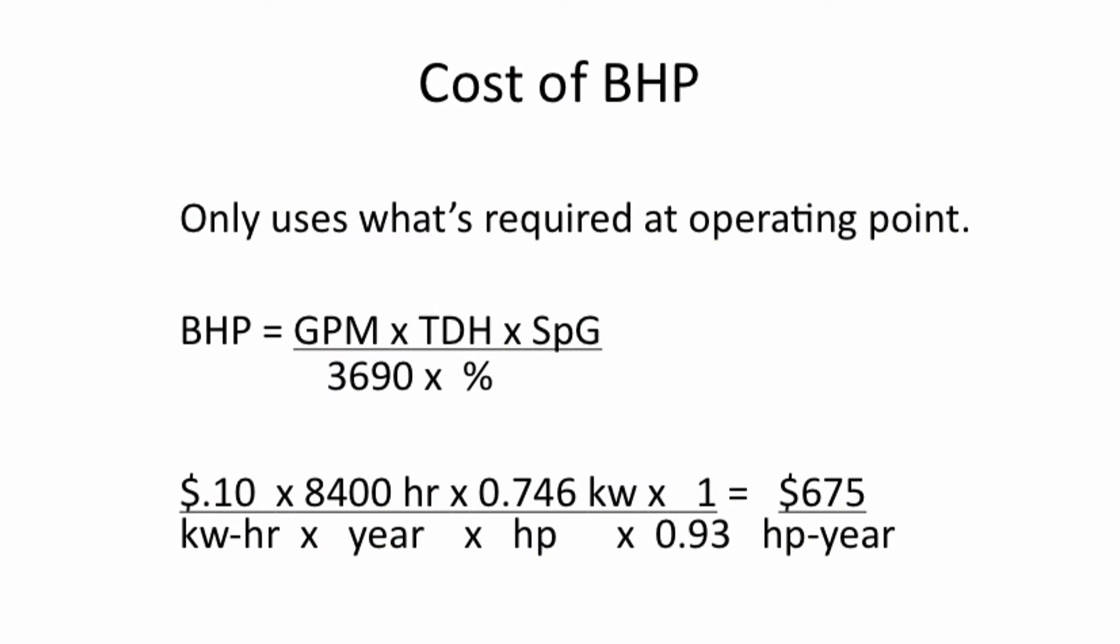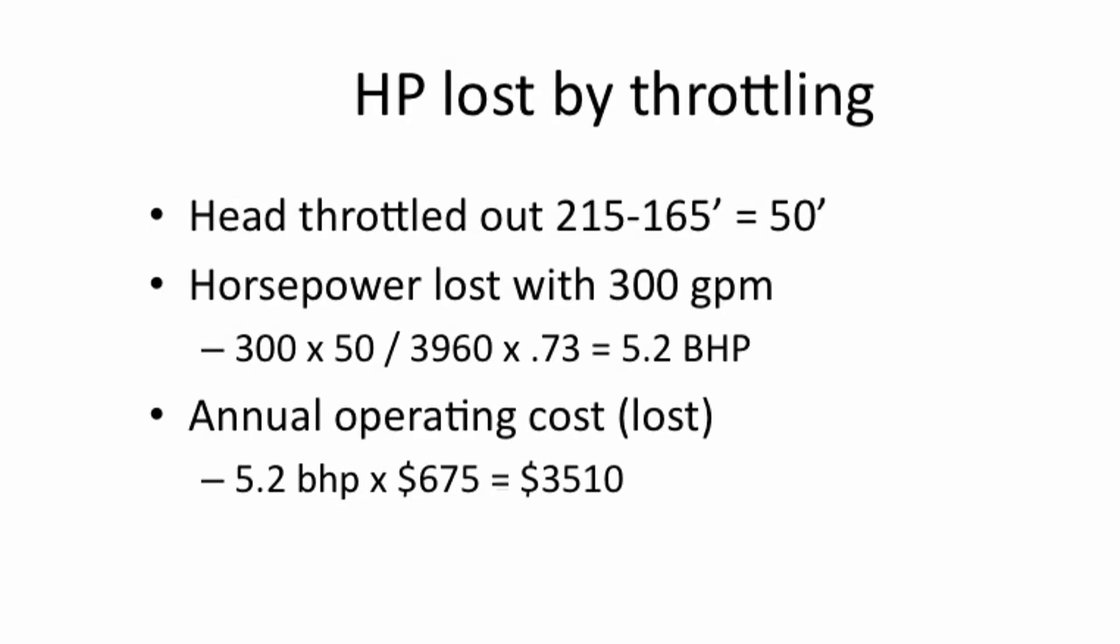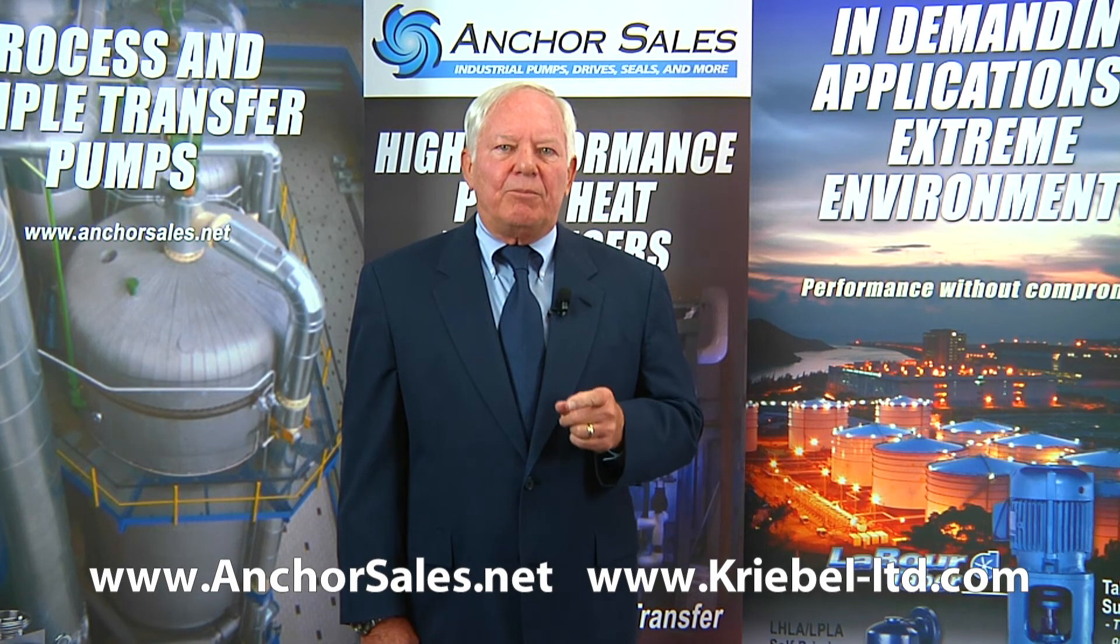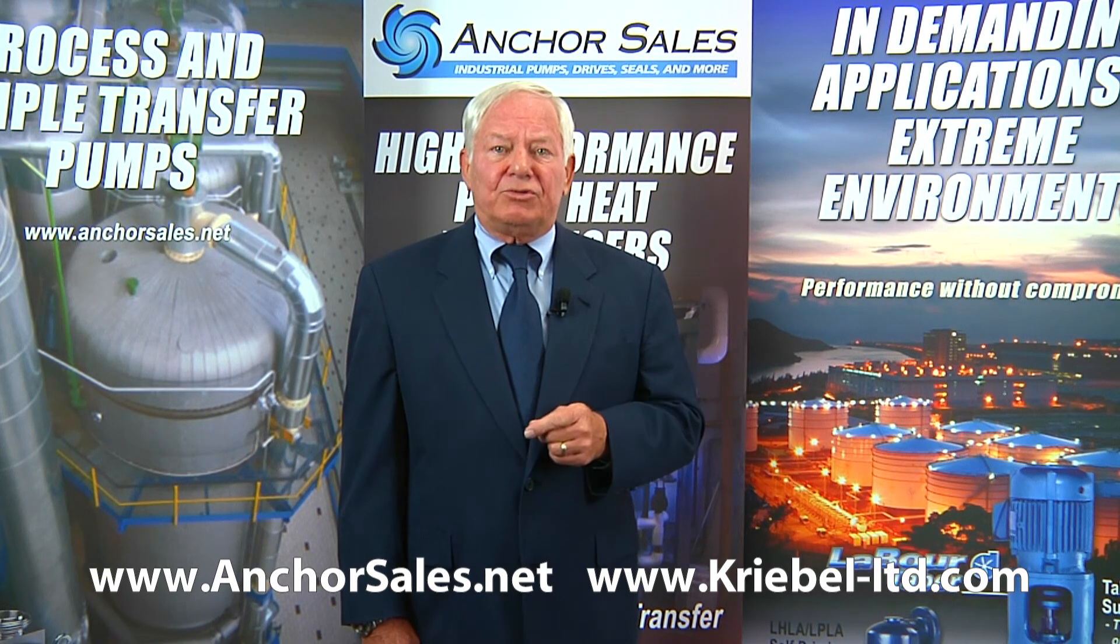The cost of a horsepower is shown here for $0.10 per kilowatt hour and for an 8,400 hour year, and with a motor efficiency of 93%, and in this case it's 5.2 additional horsepower. This horsepower is being wasted every minute the pump runs, and at $0.10 a kilowatt hour and 24-7 operation, this would be $3,510 per year. That's a lot of money for a pump and motor that might only cost $2,500.